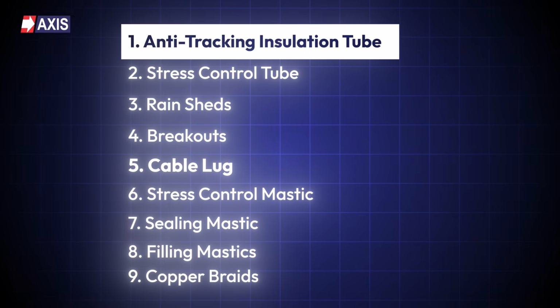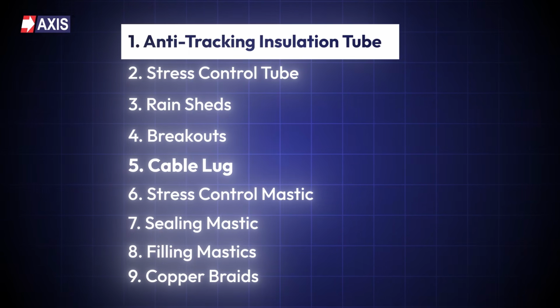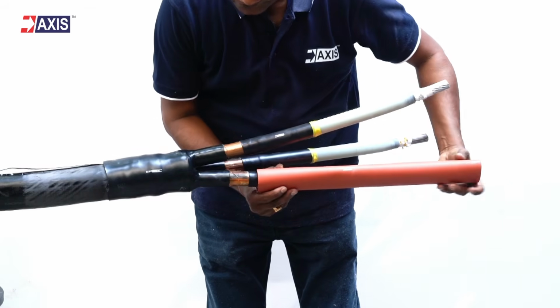First of all, the anti-tracking insulation tube. This tube is made from cross-linked polyolefin with resistance to tracking and erosion. It protects the termination surface from leakage currents caused by moisture, dust, and pollution. By forming a durable outer insulation layer, it also prevents surface discharge and flashover.